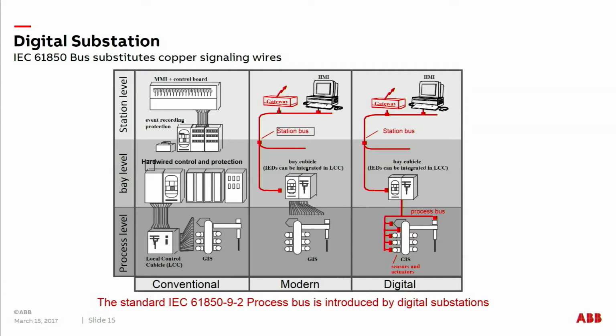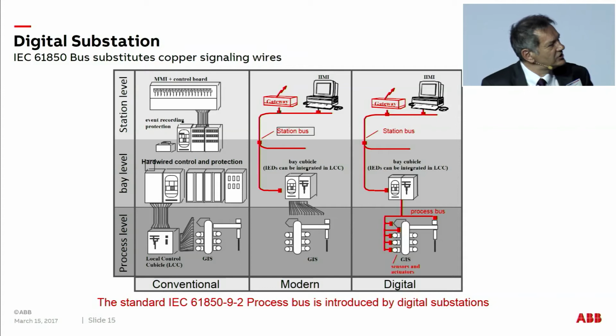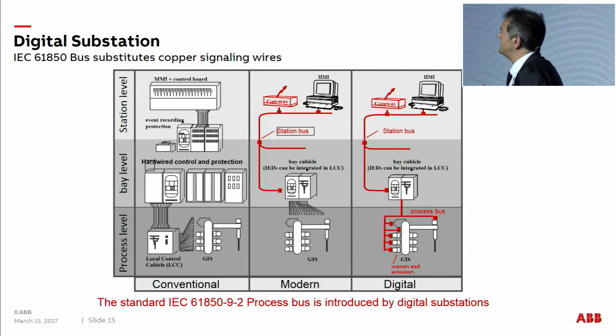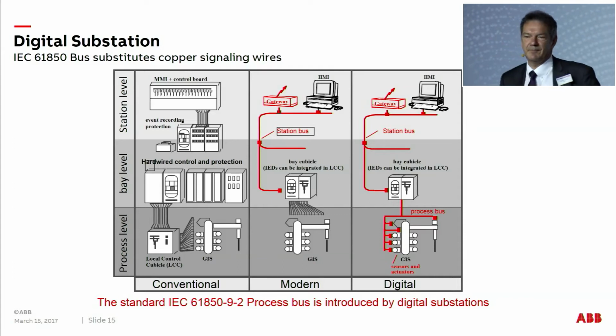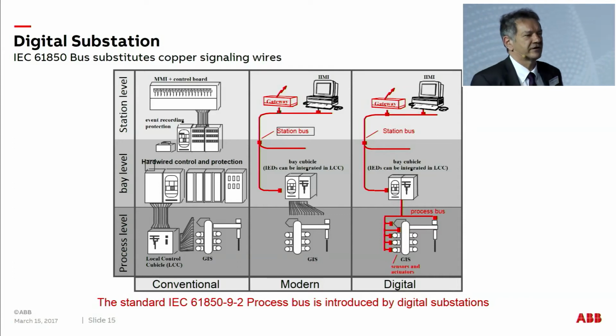What utilities buy today is what you see in the middle—we call it modern. Over the last 20 years, utilities have agreed to change the whole station level up to control and protection, replacing all the wiring at the station level with fiber optic communication buses. This has been happening over the last 15 to 20 years, and today a utility almost always buys what we call a modern substation.